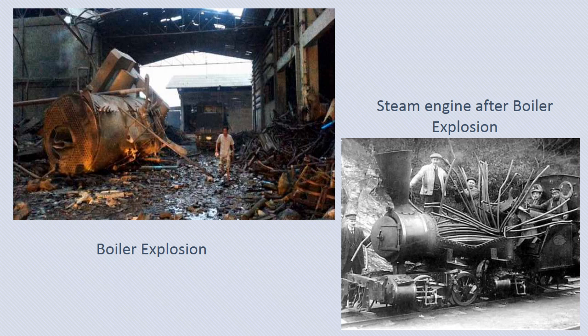Yeah, I told you about boiler explosion. No? So this is the real site of a boiler explosion in an industry. It is my better advice that if anything is under the worst condition, where we have to supply more fuel to the boiler to give the required steam, that is, if it is crossing 50% more fuel consumption, then it is wise to stop the unit and go with a new boiler unit, so that you can save people as well as the industry itself.